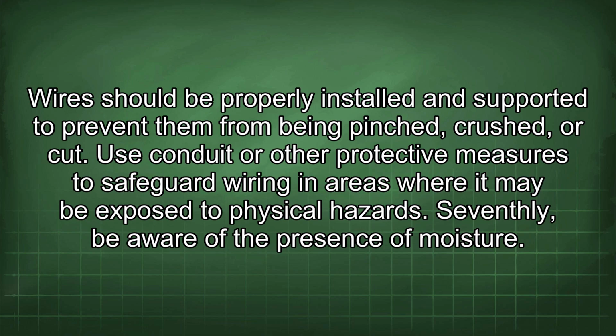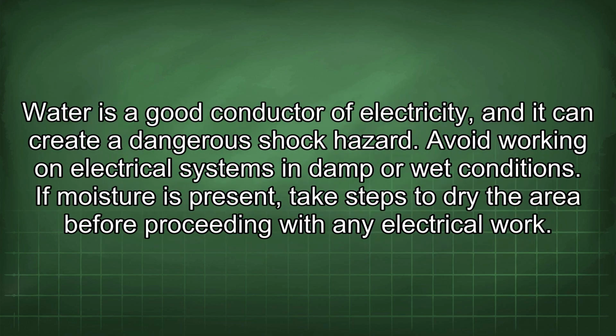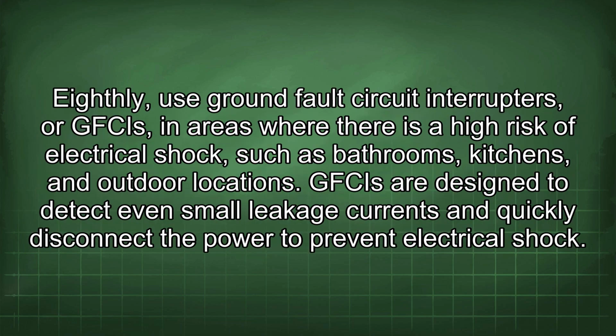Seventhly, be aware of the presence of moisture. Water is a good conductor of electricity and it can create a dangerous shock hazard. Avoid working on electrical systems in damp or wet conditions. If moisture is present, take steps to dry the area before proceeding with any electrical work. Eighthly, use ground fault circuit interrupters, or GFCIs, in areas where there is a high risk of electrical shock, such as bathrooms, kitchens, and outdoor locations. GFCIs are designed to detect even small leakage currents and quickly disconnect the power to prevent electrical shock.